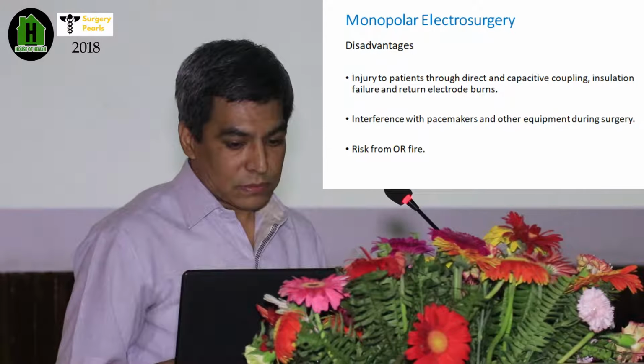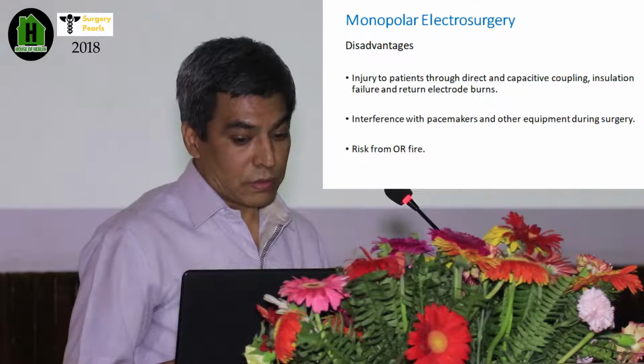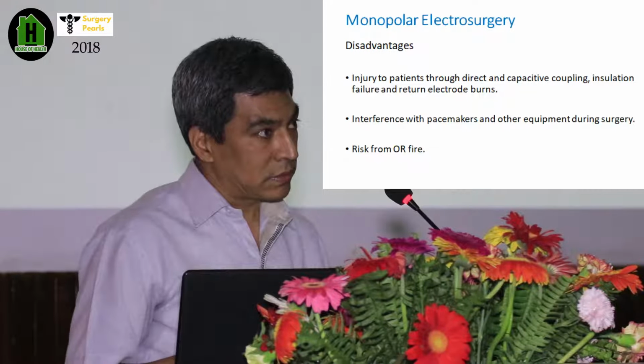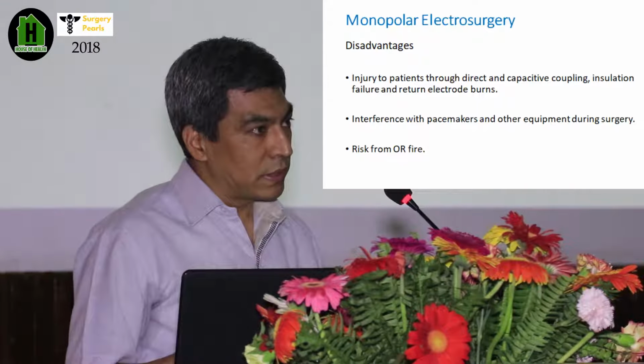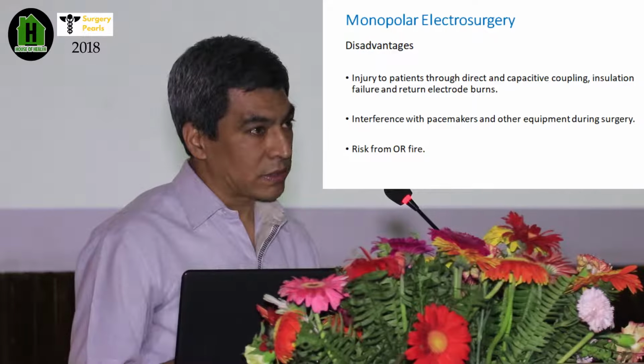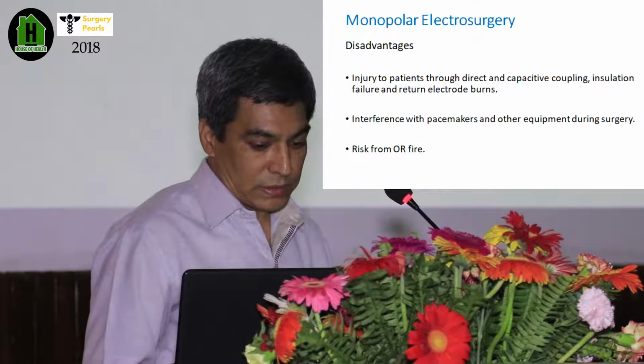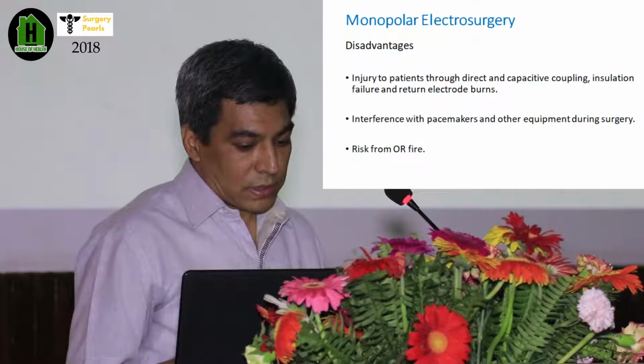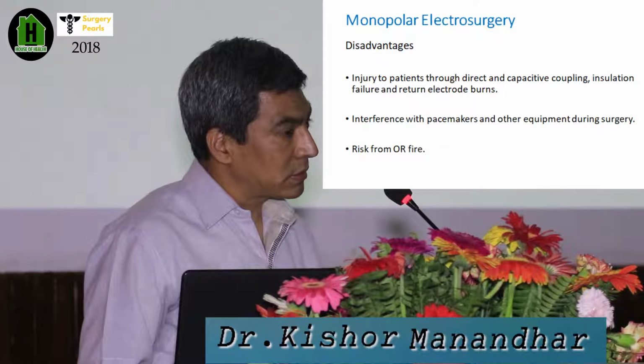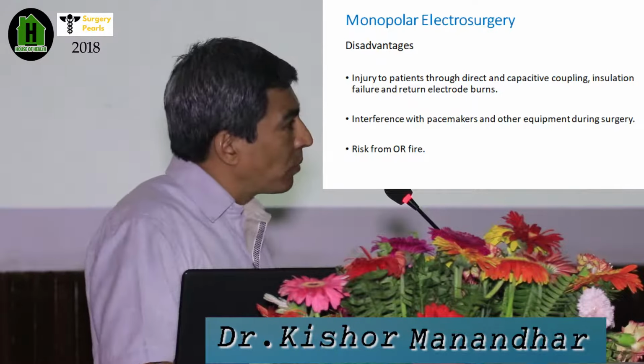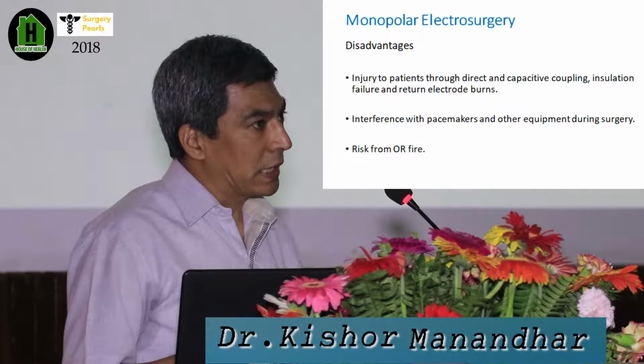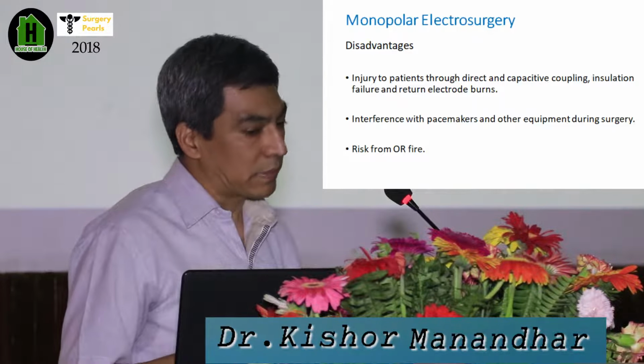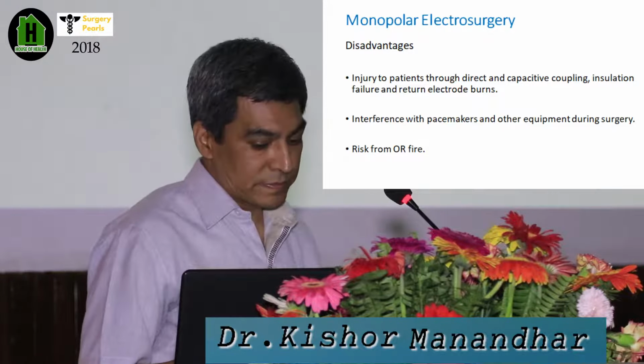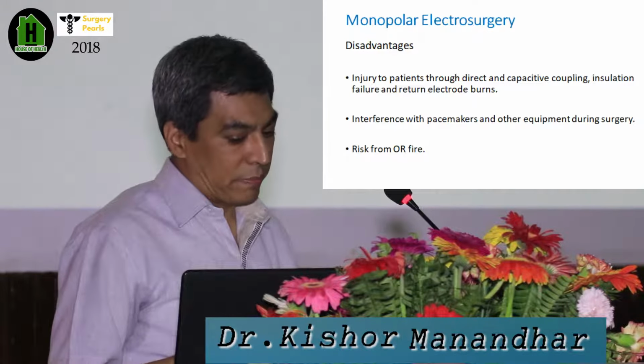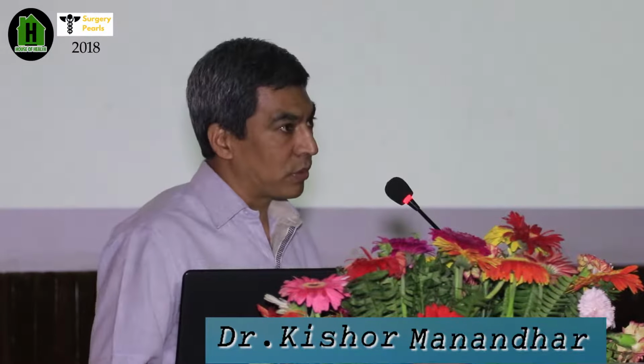However, it has some disadvantages also. It can injure the patient through direct or capacitive coupling effect. If there is insulation failure, a lot of morbidities will come in. And there is another thing, burns due to the return electrodes. While you are using the monopolar, you have to take care about electrical devices implanted in the patient, such as pacemakers or other devices which are electrically active. And there is always a risk of flame or fire in the OT while using the monopolar.